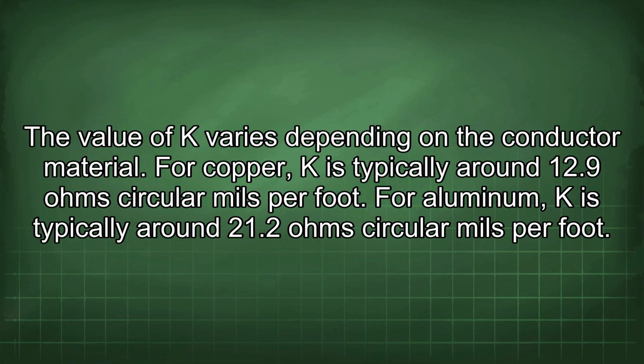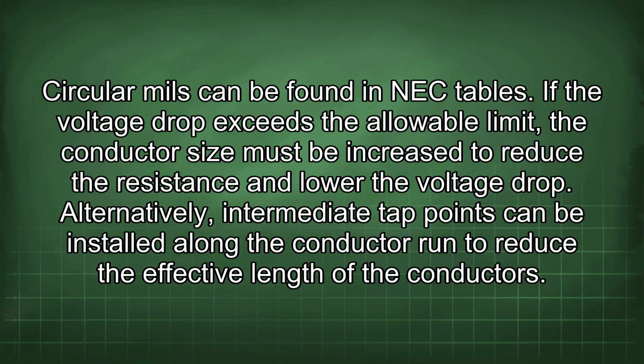The value of K varies depending on the conductor material. For copper, K is typically around 12.9 ohms circular mils per foot. For aluminum, K is typically around 21.2 ohms circular mils per foot. Circular mils can be found in NEC tables. If the voltage drop exceeds the allowable limit, the conductor size must be increased to reduce the resistance and lower the voltage drop. Alternatively, intermediate tap points can be installed along the conductor run to reduce the effective length of the conductors.